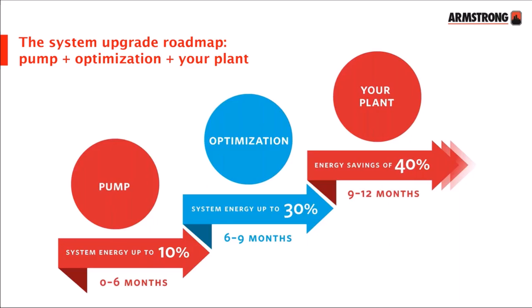And then finally, we get to the larger plant, your chillers and your boilers. But at this point, because we've been using our pump manager and our remote monitoring, we know not just the building load, we also understand the load profile. So what usually happens at this point is we end up reducing the size of the replacement chiller over and above what's already installed, which is a big benefit from a CapEx point of view. But we can also then select the right chiller or boiler at its best efficiency, so it can spend longer at its highest efficiency, and therefore you get longer savings or better savings.